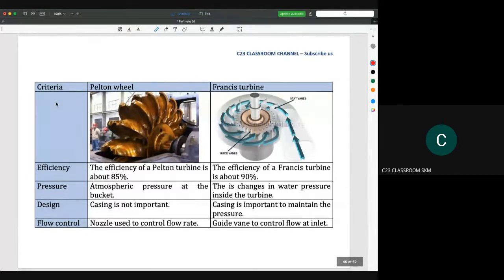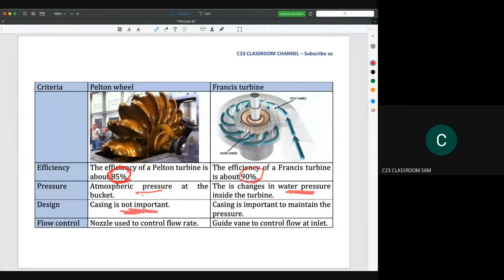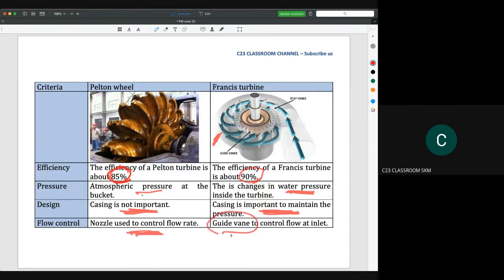Pelton wheel efficiency is around 85% because it is open to atmospheric pressure, while Francis turbine efficiency may reach 90%. For Pelton wheels, the casing design is not critical, but for Francis turbines the casing is an important component — any leakage reduces pressure and impairs performance. For flow control, the Pelton wheel uses a nozzle to control flow rate, while the Francis turbine uses guide vanes, which are fixed blades that ensure water enters the runner blades at a specific angle.